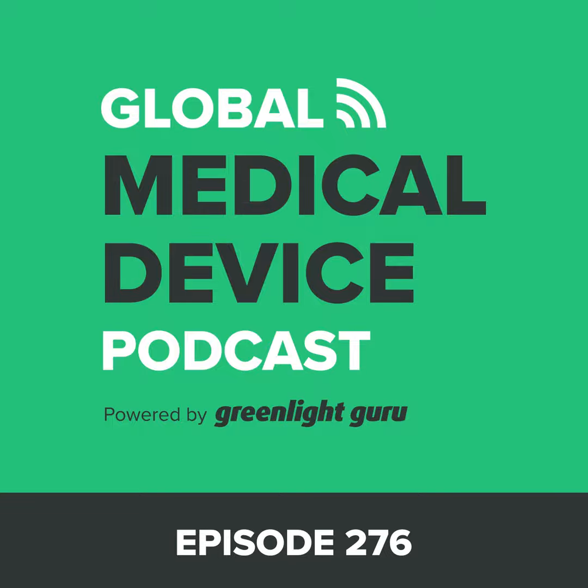And most recently, in May of 2022, a similar deadline took place for the in vitro diagnostics. So those now Class A products that are self-certified, as of the date of application in May, it was another bundle of energy that had to be put together to meet all that. Now, when you get beyond the Class Is and you start to get into Class 2s and 3s, the 2As and Bs and so on, now you need to engage a notified body to evaluate your documentation.